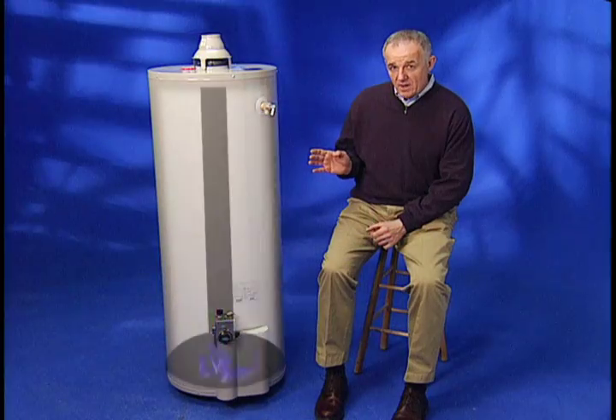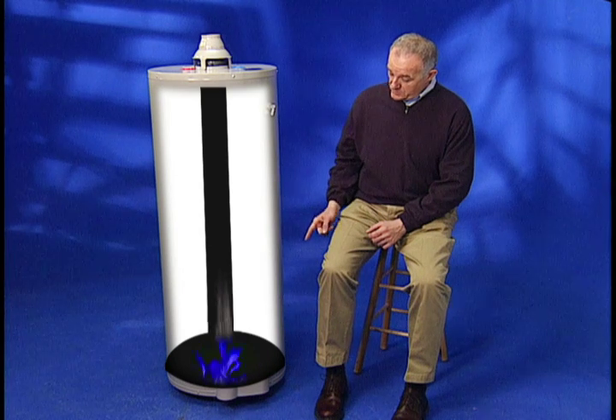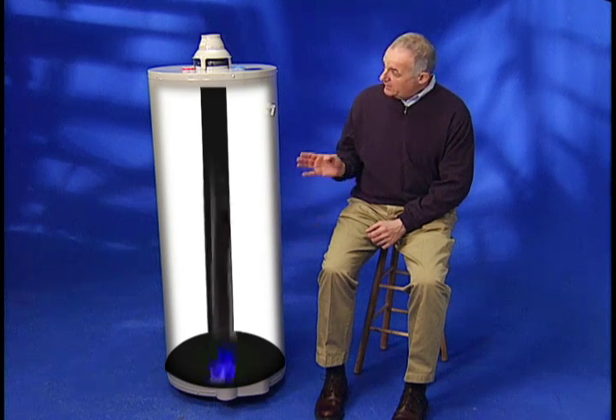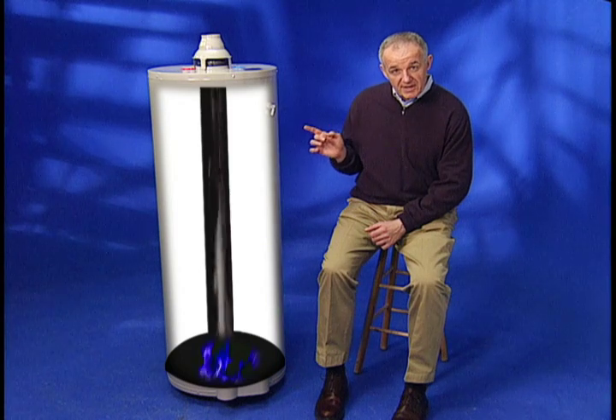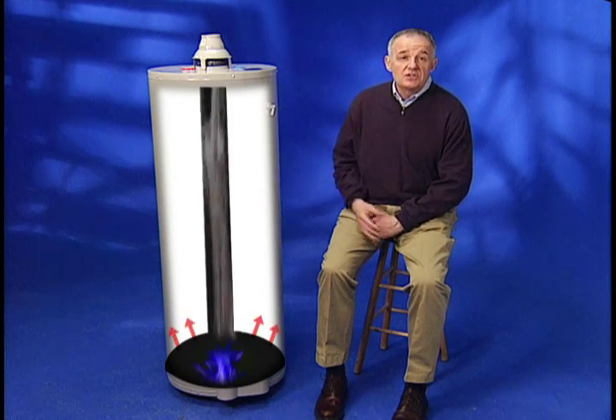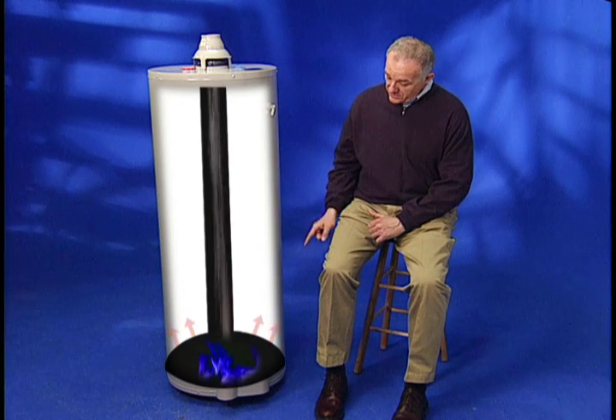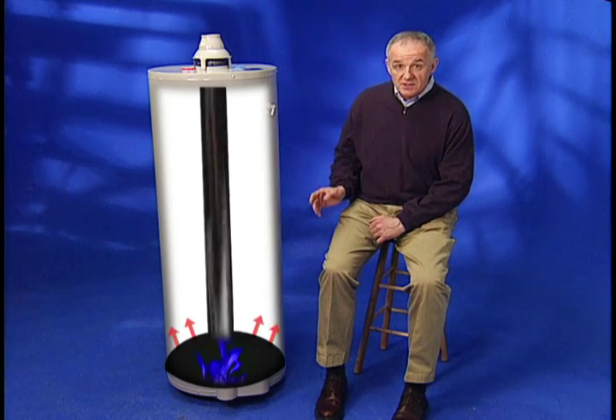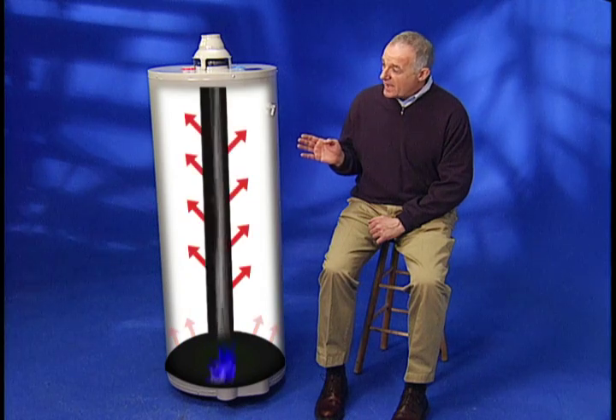In a conventional gas water heater, hot gases produced by the burner vent vertically through a flue tube running through the center of the tank. Most of the heat generated is transferred to the water through the tank bottom, but heat also transfers from the hot gases rising through the flue tube.